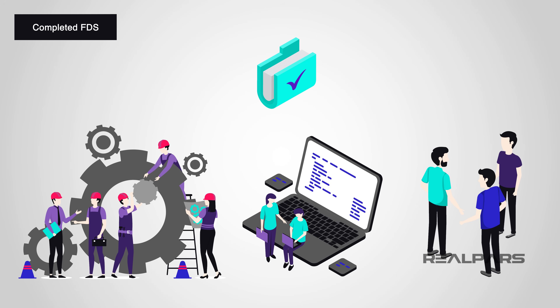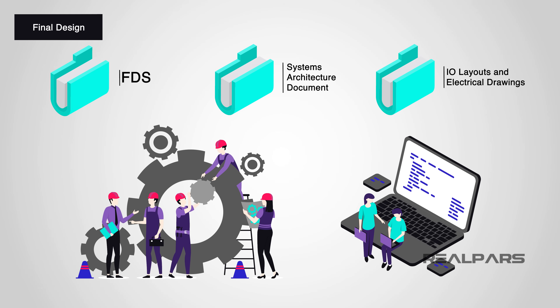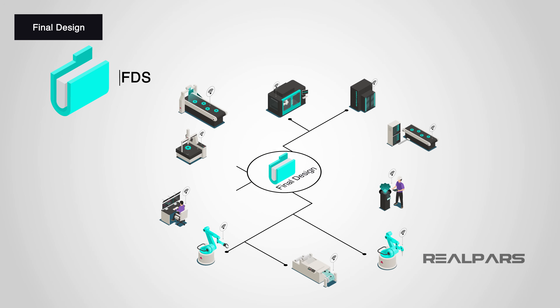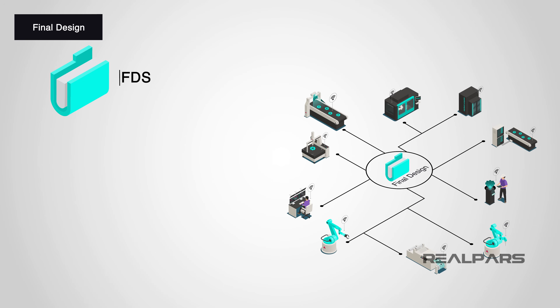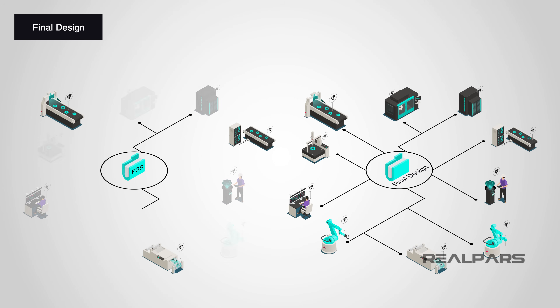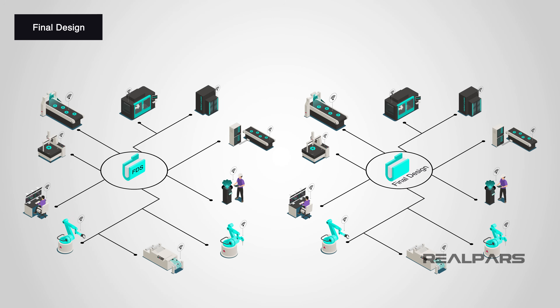In a typical industrial software engineering lifecycle, the Functional Design Specification describes what has to be implemented. The next document after this may be a Systems Architecture document, describing how the functions will be realized using the chosen PLC controller. This in turn will help produce the I/O layouts and electrical drawings. Finally, when the testing phase is performed, the actual behavior of the final system is compared against the expected behavior as defined in the Functional Specification.